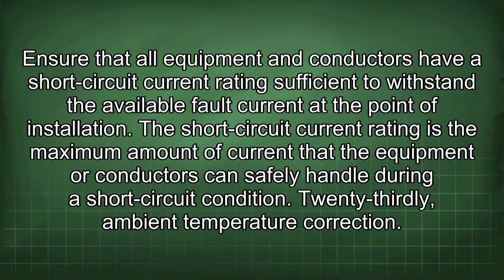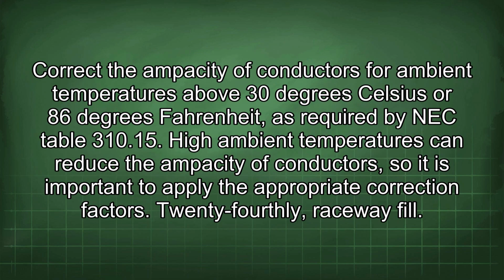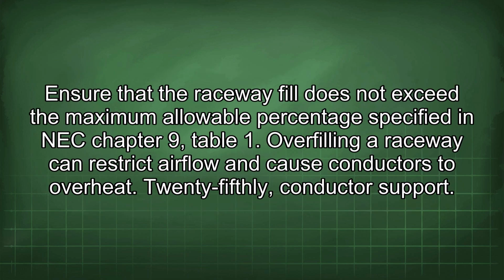23rd, ambient temperature correction. Correct the ampacity of conductors for ambient temperatures above 30 degrees Celsius or 86 degrees Fahrenheit, as required by NEC Table 310.15. High ambient temperatures can reduce the ampacity of conductors, so it is important to apply the appropriate correction factors. 24th, raceway fill. Ensure that the raceway fill does not exceed the maximum allowable percentage specified in NEC Chapter 9, Table 1. Overfilling a raceway can restrict airflow and cause conductors to overheat.